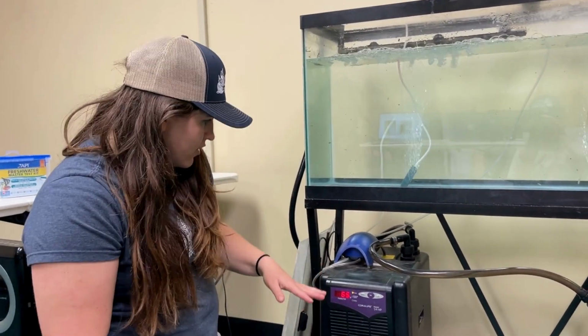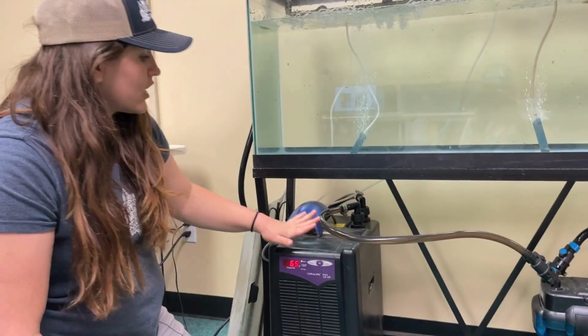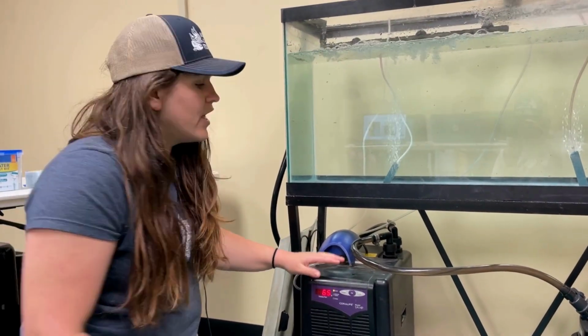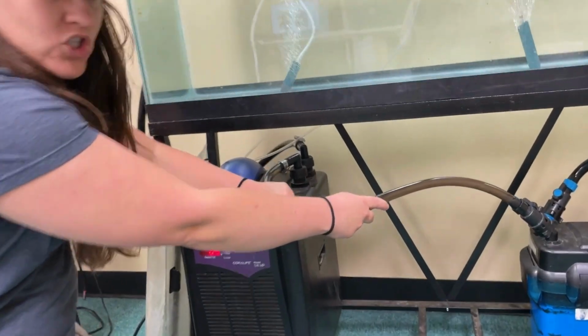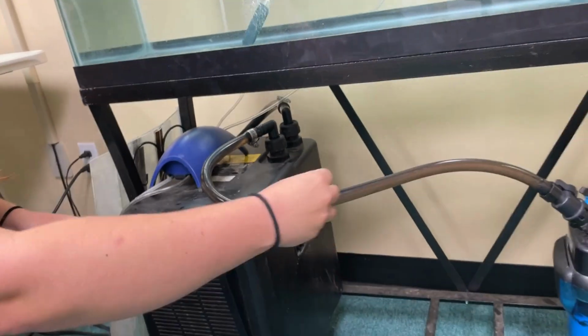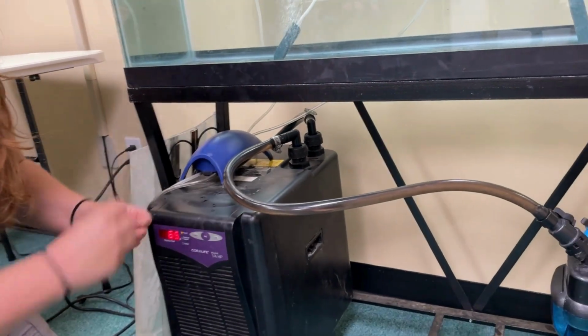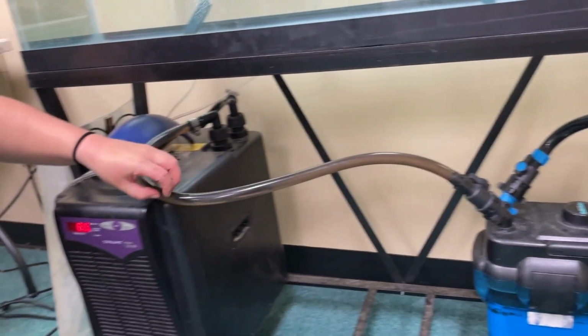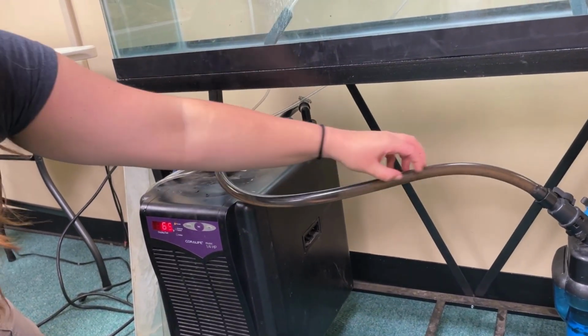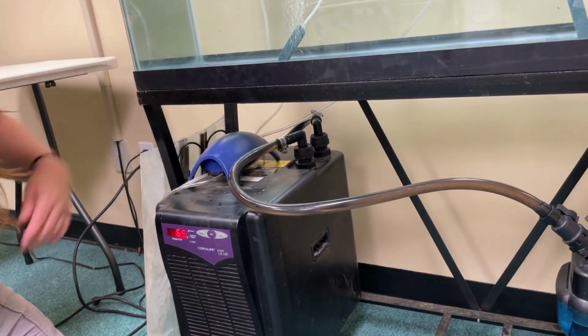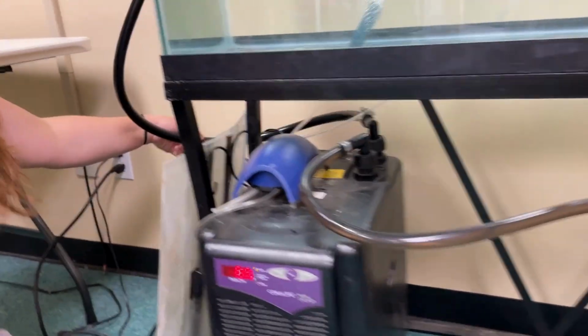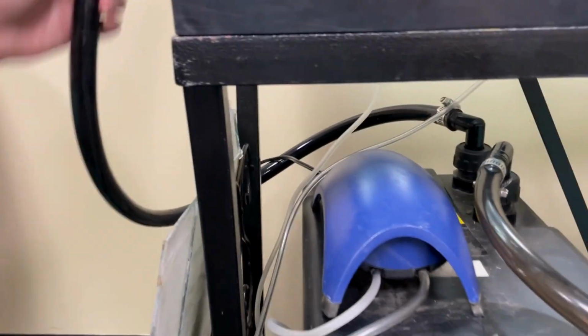the first thing you want to do is check the hoses coming in and out of the chiller. If they have a big corkscrew or kink in them, the water won't move fast enough to be chilled. This is about as much curve as I'd want in this line, not much more than that, and I check the same back here, double checking there's no kink.